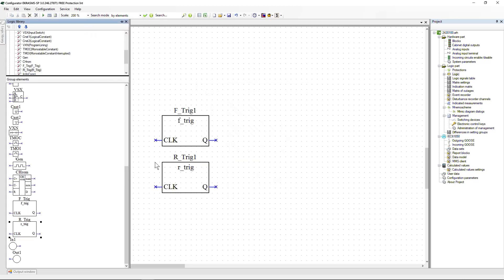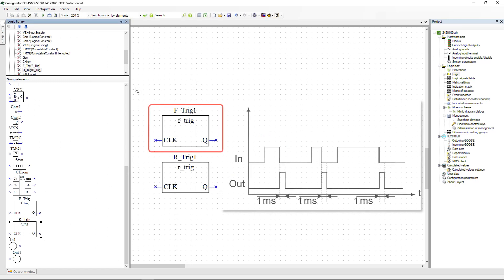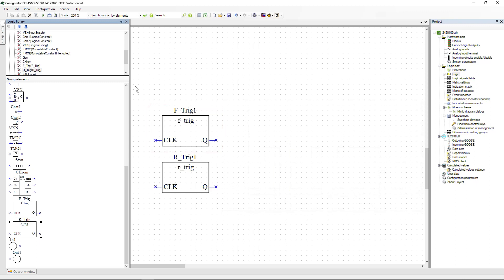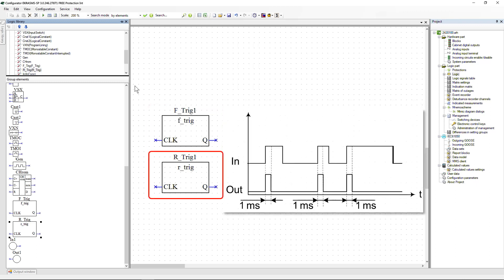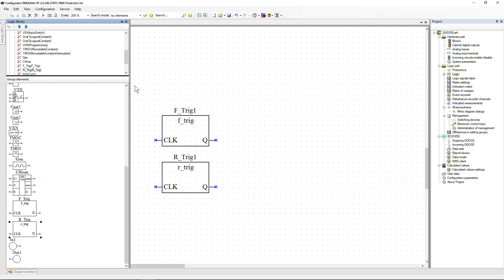Pulse formers with non-adjustable pulse duration: the F Trig element generates a pulse with a duration of one millisecond when the signal at the element's input changes from logical one to logical zero. The R Trig element generates a pulse with a duration of one millisecond when the signal changes from logical zero to logical one. These pulse formers are used for technological purposes where it is not necessary to adjust the pulse duration.